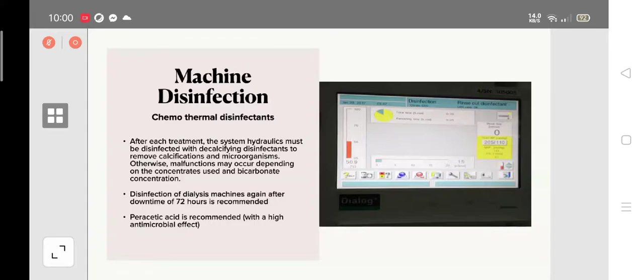To help ensure patient safety, machine disinfection is done with chemothermal disinfectants. After each treatment, the system hydraulics must be disinfected with decalcifying disinfectant to remove calcification and microorganisms. Otherwise, malfunction may occur depending on the concentrates used and bicarbonate concentration. Disinfection of the dialysis machine again after a downtime of 72 hours is recommended. Peracetic acid is also recommended for its antimicrobial effect.